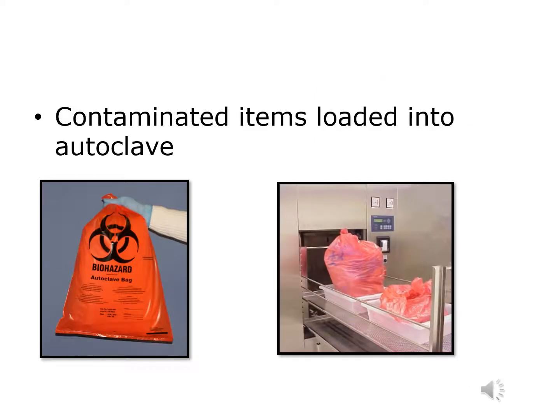The items that are sterilized in an autoclave have to be bagged or contained in some kind of tray. The bags are generally this orangish color shown on the slide, or red. Rarely are they clear, but there are some. And they'll always say biohazard, they'll have the symbol, and they should say autoclave safe. They're made to withstand those temperatures. Instruments and tools can be autoclaved in metal trays.